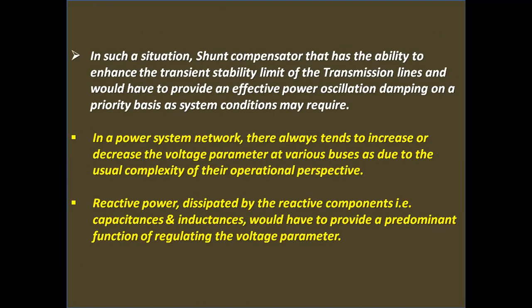In such a situation, a shunt compensator has the ability to enhance the transient stability limit of the transmission lines and provide effective power oscillation damping on a priority basis as system conditions may require. In a power system network, the voltage at various buses always tends to increase or decrease due to the usual complexity of the operational perspective. Reactive power, dissipated by the reactive components, that is capacitances and inductances, has a predominant function of regulating the voltage parameter.